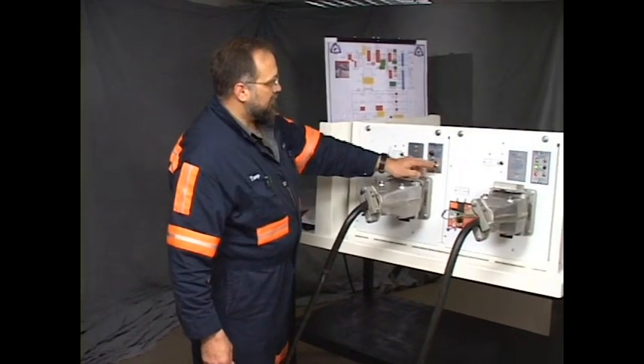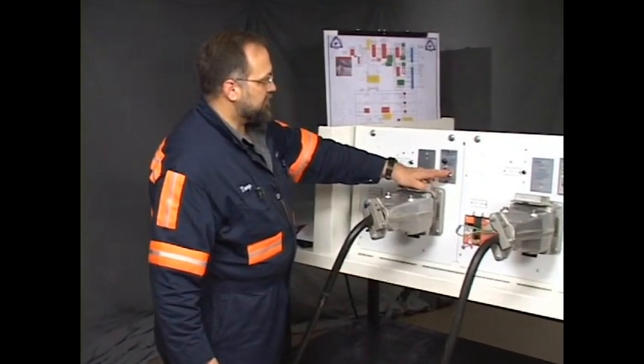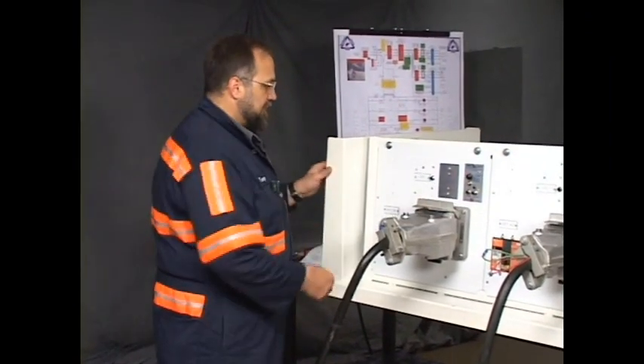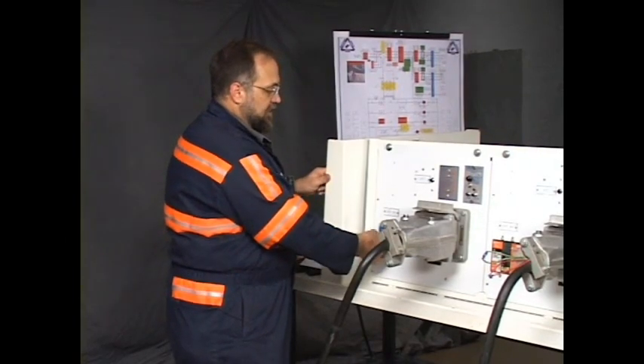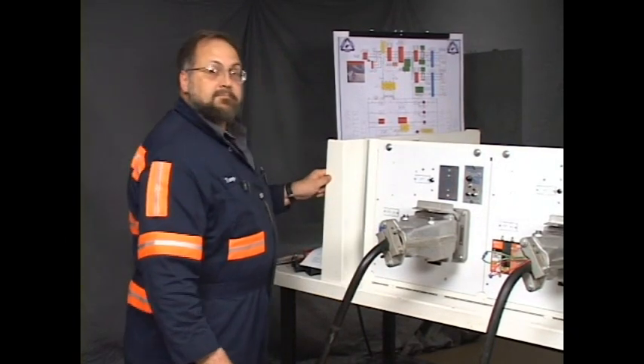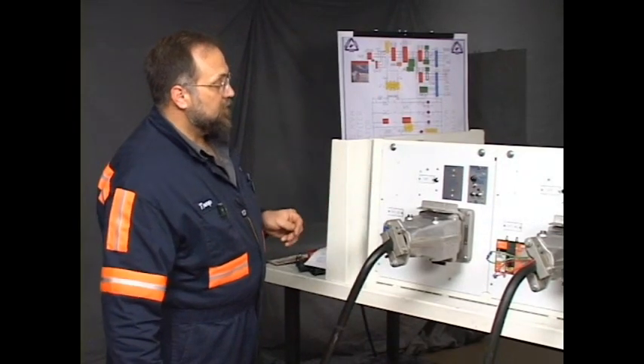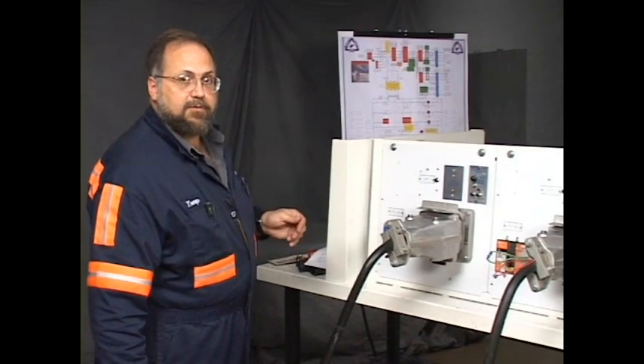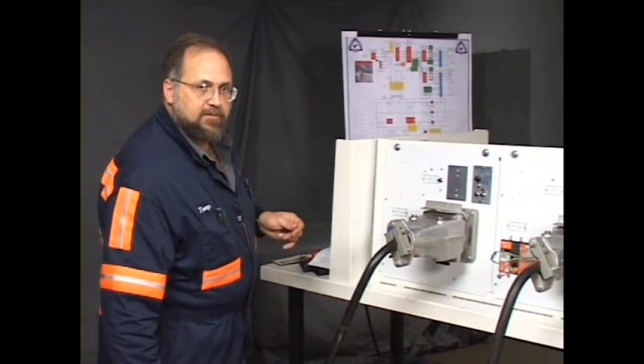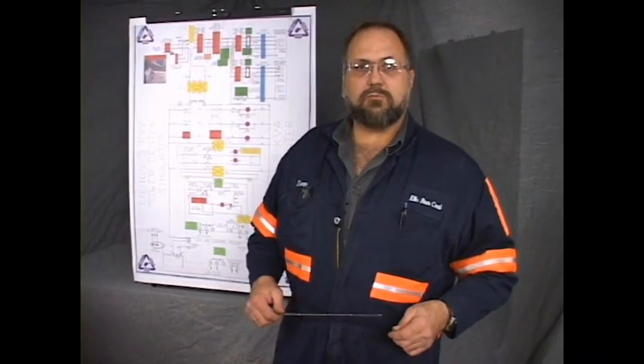Well, we have a ground monitor circuit. We can apply the test switch and it trips, reset, sets back up. Try to set it, and it won't set. So we obviously have a problem with the circuitry inside the power center. We'll have to go to the other side to check this. Well, we discussed earlier the importance of doing all possible troubleshooting with power off, making continuity tests. But this particular circuit, to properly troubleshoot it, involves the closing of a relay, and that requires the power to be on. So we're going to have to change our methods just a little bit.